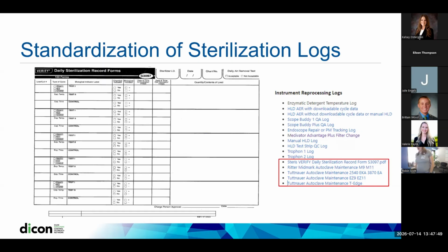The next log we have is our standard sterilization log to record all of the necessary components required for items that undergo sterilization. And so here we're looking for the autoclave ID, because some clinics may have more than one. We're looking for the load number, lot number of both the test and the control BI, the result of the chemical indicator from the test biological indicator, the result of both the test and control BI, and then of course time, date, and initials of those staff who read the BIs once they were incubated, and the contents of the load.